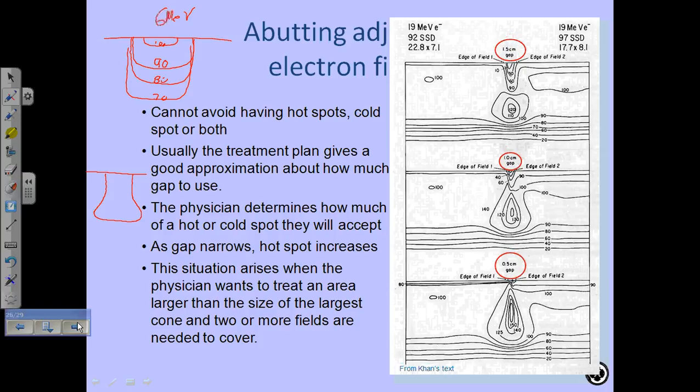And as it gets to RP, and the energy starts dropping, they start to scatter sideways more. And so the isodoses look more like a bell for 20 MeV. There's more side scatter at deeper depths, not at shallow depths, but at deeper depths. That's where the 120 comes from. This one here, abutting with another one that's next to it, the bells are going to add up. The diverging isodoses are going to add up. Okay, that's where that comes from.